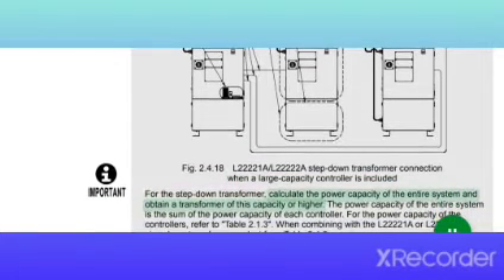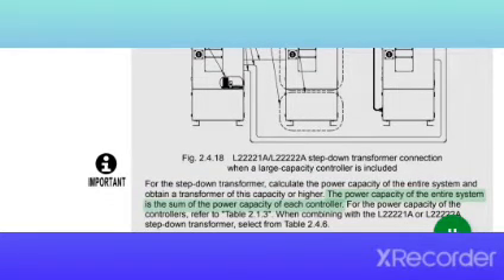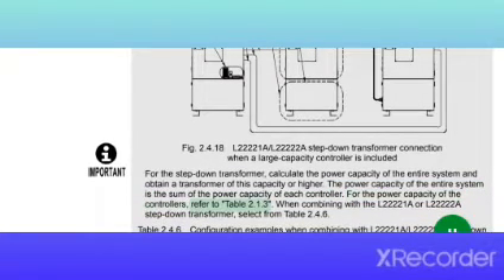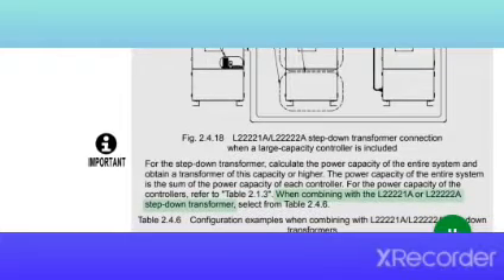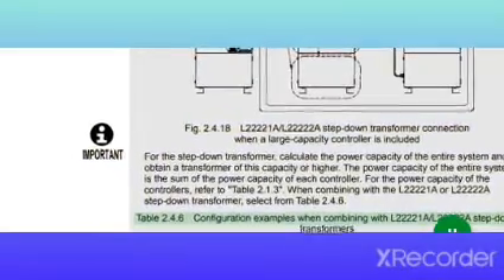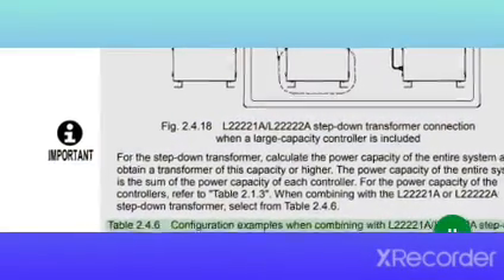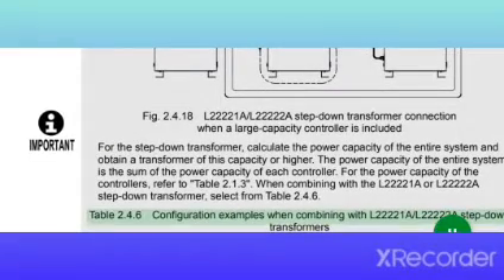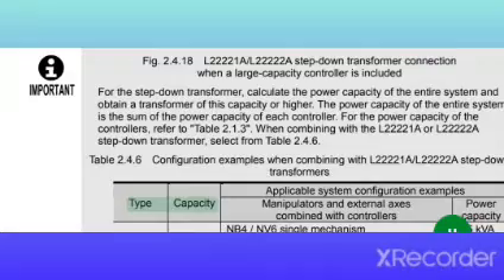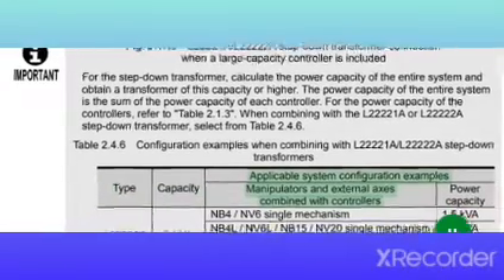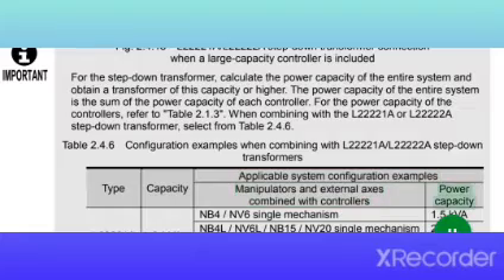For the step-down transformer, calculate the power capacity of the entire system and obtain a transformer of this capacity or higher. The power capacity of the entire system is the sum of the power capacity of each controller. For the power capacity of the controllers, refer to Table 2.1.3. When combining with the L22221A or L22222A step-down transformer, select from Table 2.4.6. Table 2.4.6 Configuration examples when combining with L22221A/L22222A step-down transformers. Type, capacity. Applicable system configuration examples, manipulators and external axes combined with controllers. Power capacity.